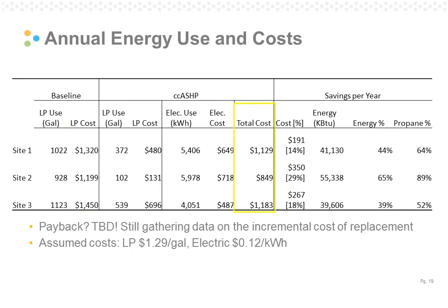When you add in the air source heat pump, the amount of LP being used goes down drastically. You do now have the electric use, but the total cost still comes down. So we're seeing several $100s of savings at each site, with the most money so far being saved at Site 2.